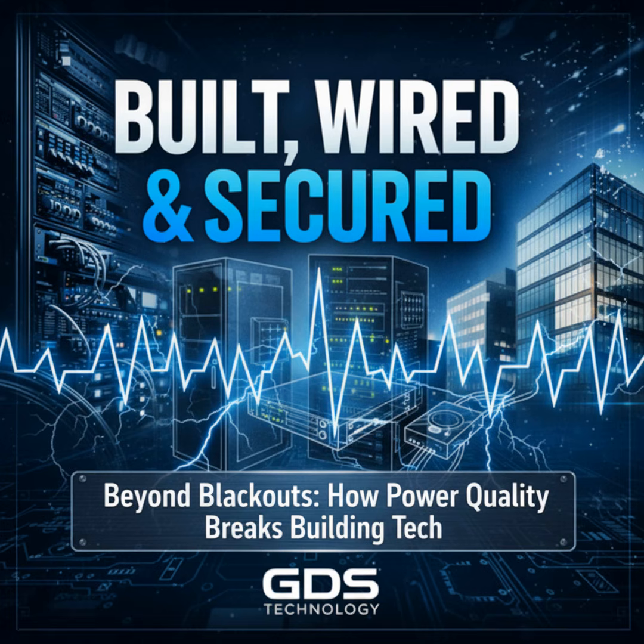to call the landlord. From an operational standpoint, that scenario is frustrating because the first instinct is to point at big visible failures, a generator test, a breaker trip. But what breaks everything quietly is power quality. Voltage sags, momentary transients, harmonics. They don't always blow fuses, but they age equipment, confuse UPS logic, and create intermittent faults that are hard to reproduce. Before we get into fixes, let's set the record straight.